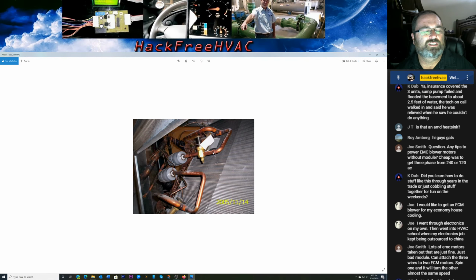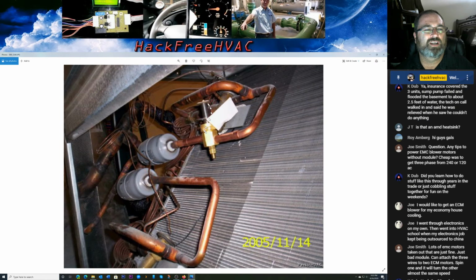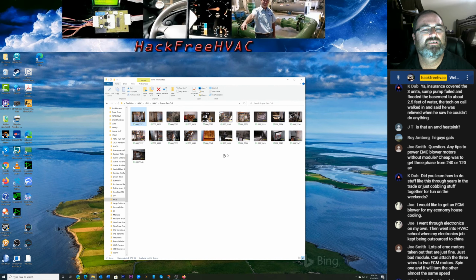So here's your two - so I added this. This is before I was soldering it in, I think. I was soldering in a solenoid right here. So basically, this didn't kick in until Y2 kicked in, and then this would come on. This always had flow, and then the second half of the coil would just get it when it went to Y2. So when it was unloaded, this would stop. So with 50% compressor, same velocity through the coil, be able to pull the oil out was the idea.